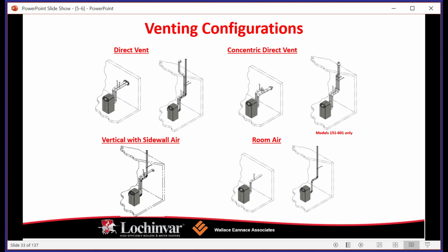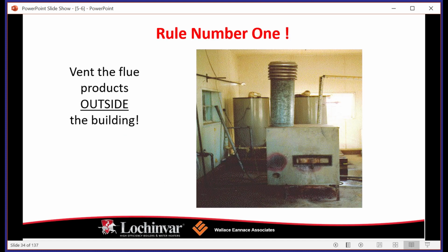You're not going to see room air for smaller applications where you have a tightly sealed room, with a couple of doors between the boiler and a fresh air source. At that point, you're going to need to look at pulling all outside fresh air.